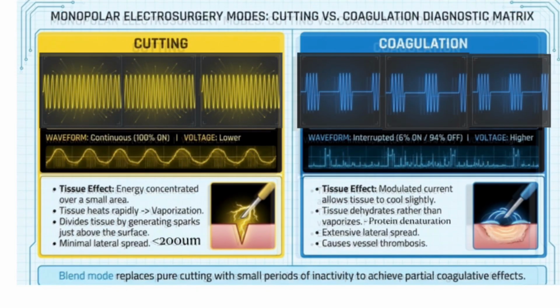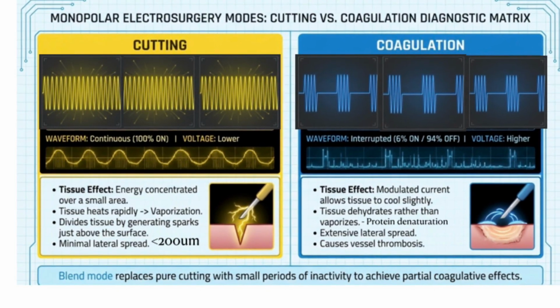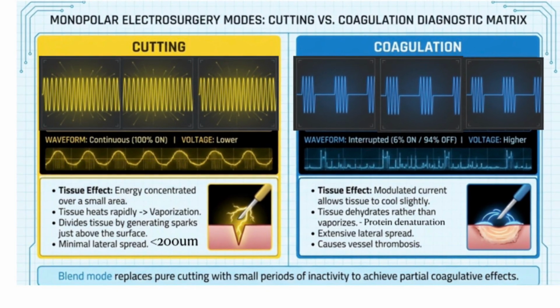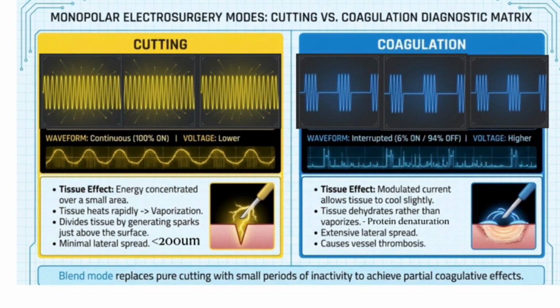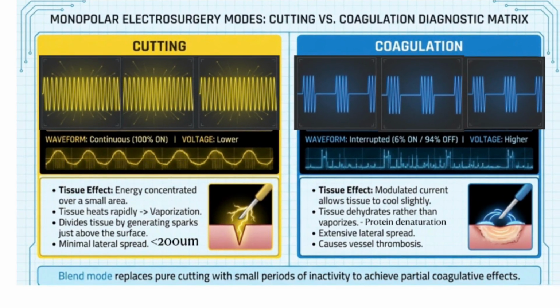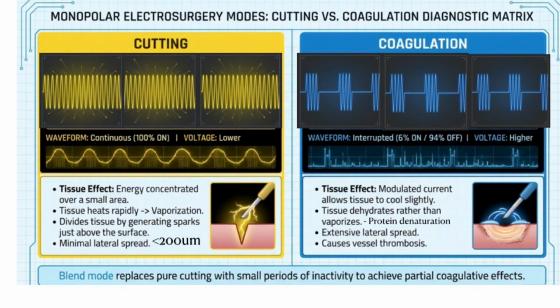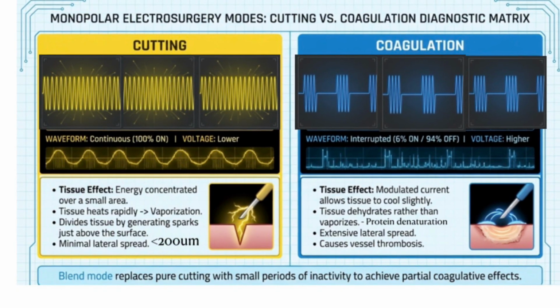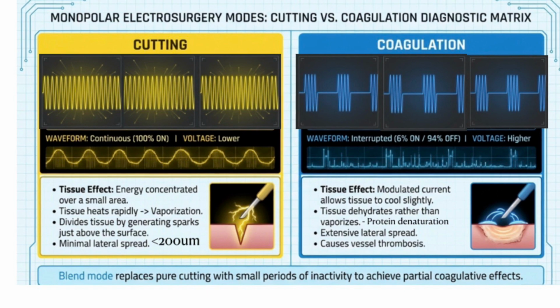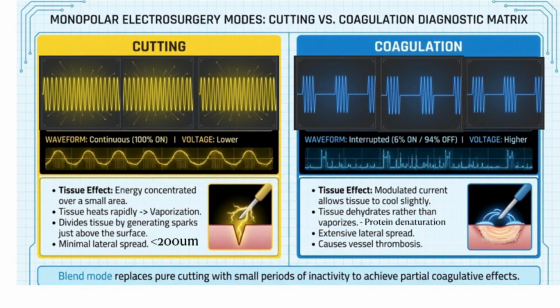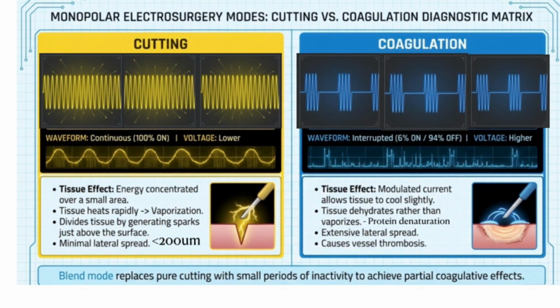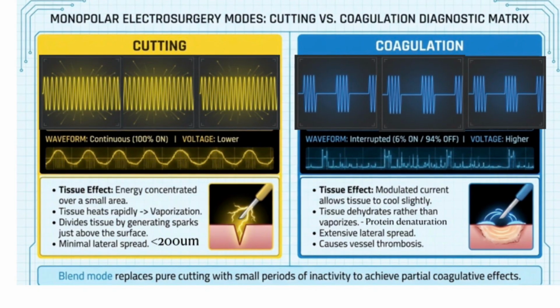In coagulation, there is interrupted flow of the current, 6% on and 94% off. The voltage is higher. The tissue effect: the modulated current allows tissue to cool slightly. The tissue dehydrates rather than vaporizes, and there is protein denaturation. There is extensive lateral spread. It causes vessel thrombosis.